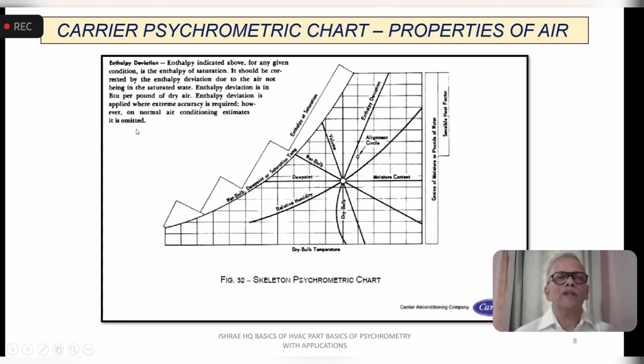Now, the explanation here is about the enthalpy values and deviations. Here it says that the wet bulb and enthalpy lines are concurrent for the range of temperatures we work with for normal air conditioning, and that's why that approximation is done. For higher accuracy, you will have to go a different way, which is the ISHRAE style. Now here you will find one alignment circle, which is in the middle of the chart. And then you will find a sensible heat ratio as the calibration. We will come to that in a moment, but that is where the difference is.